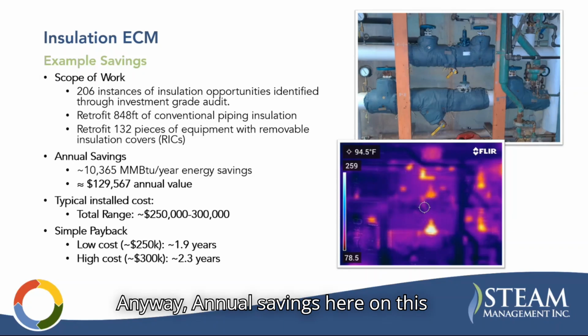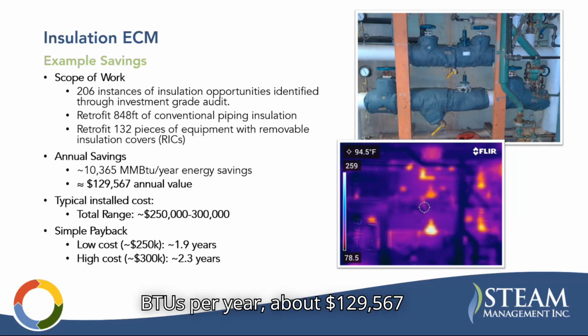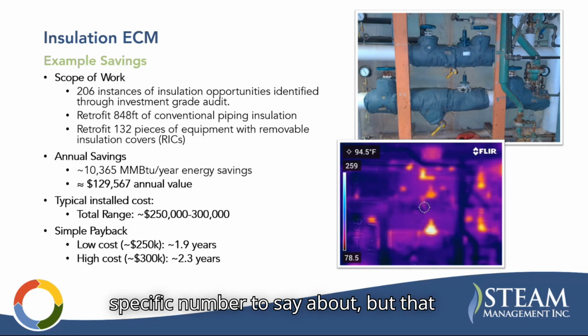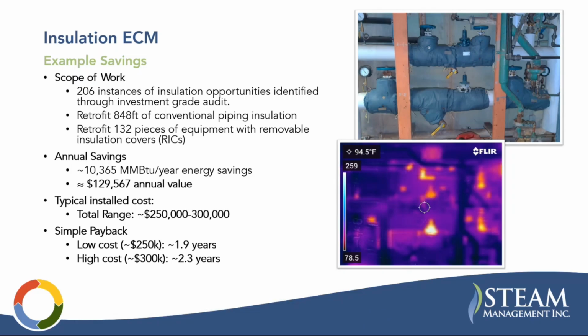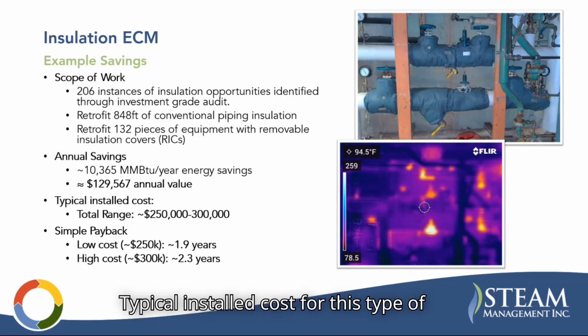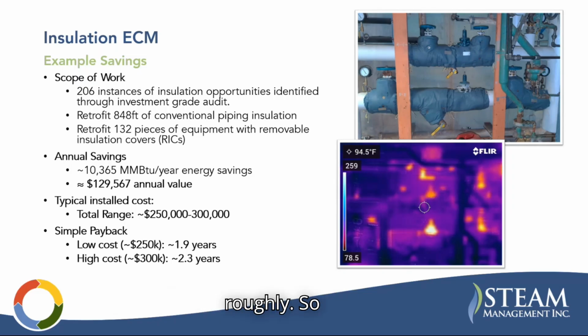Anyway, annual savings on this project were 10,365 million BTUs per year, about $129,567 annual value. That's a pretty specific number to say "about," but that was the calculated savings. Typical installed cost for this type of job is roughly $250,000 to $300,000. So payback of 1.9 to 2.3 years. That's a really good scope as well.